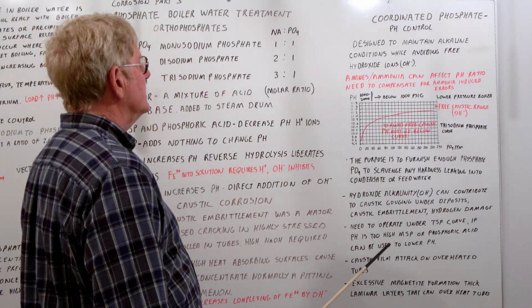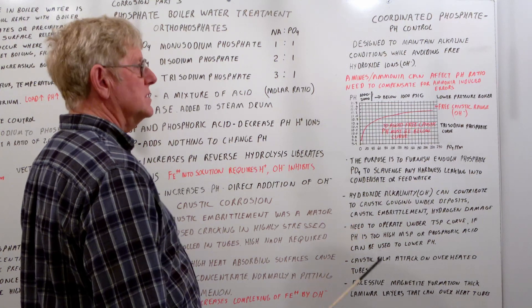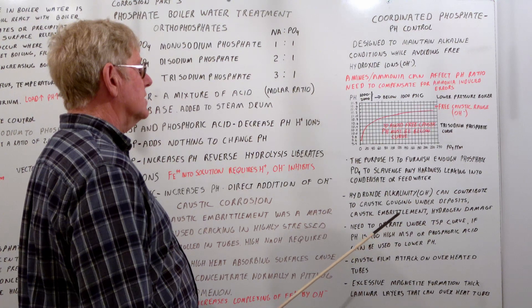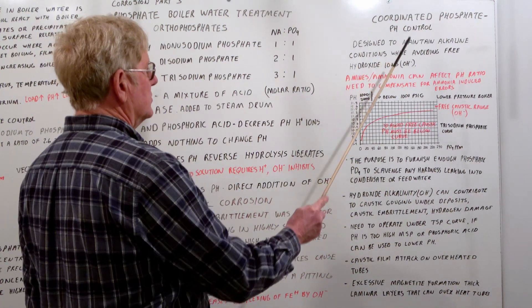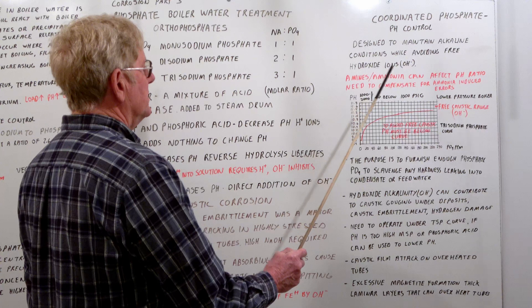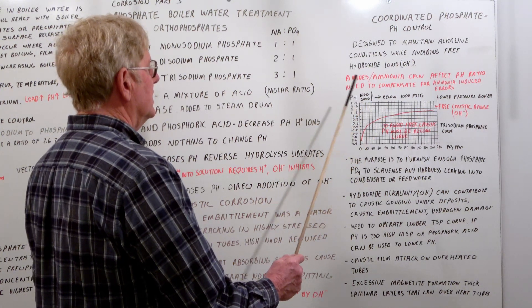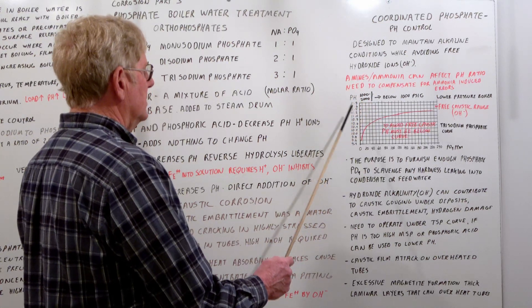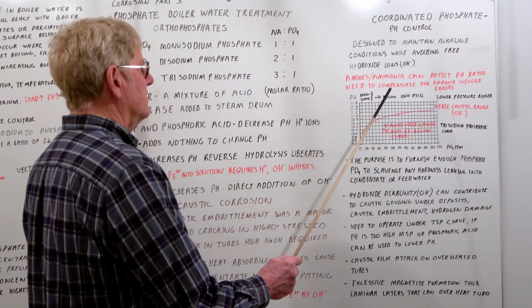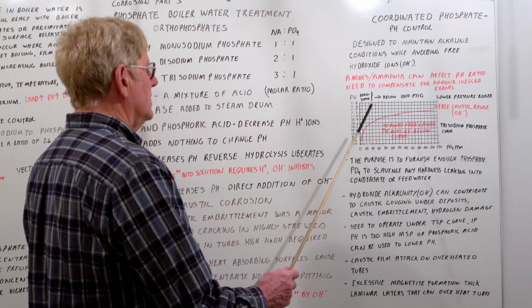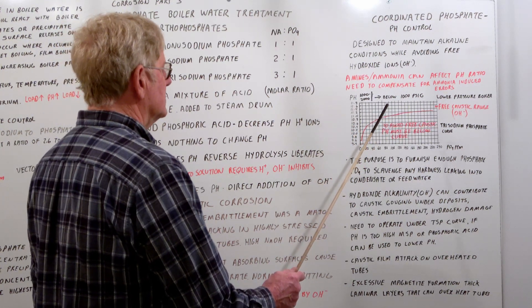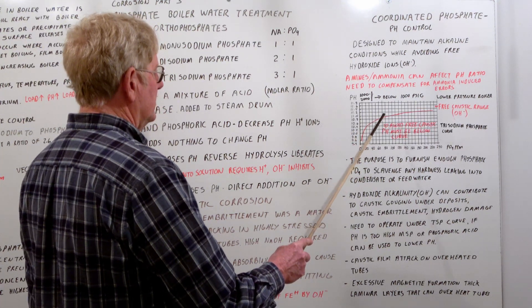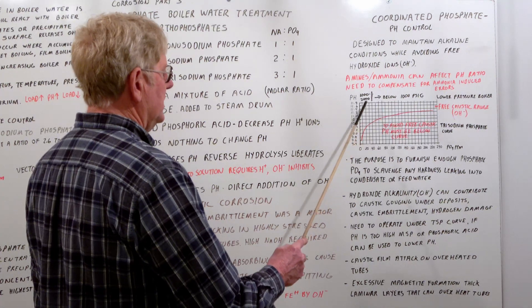This is the coordinated phosphate control. There are two types of phosphate control: coordinated and congruent. Coordinated is a pH control designed to maintain alkalinity conditions while avoiding free hydroxide ions. One thing to be aware of: amines and ammonia can affect the pH ratio. You need to compensate for ammonia-induced errors. If you add ammonium hydroxide to your condensate, it will show up in your boiler drums and skew the pH.